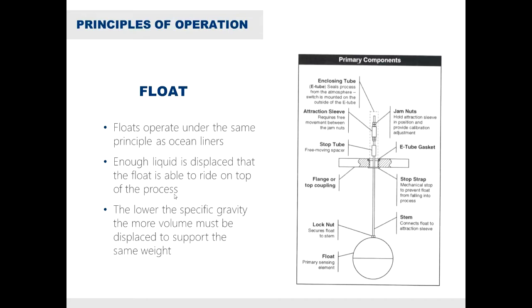You have a float, which is the primary sensing element — the device that will actually transfer all the movement to the switching element itself. That's connected to a stem, and on that stem you have an attraction sleeve, which is inside of an enclosing tube. That enclosing tube seals off the process from all the electrical switching elements and enclosure on the inside.